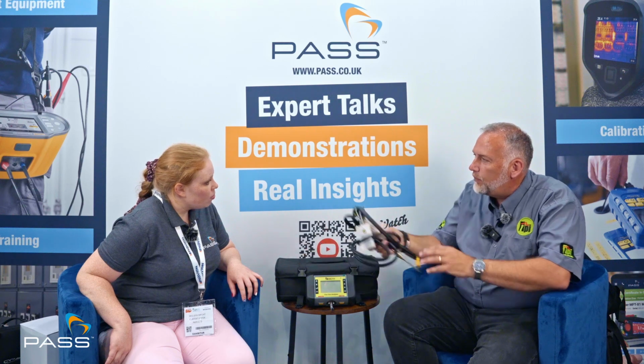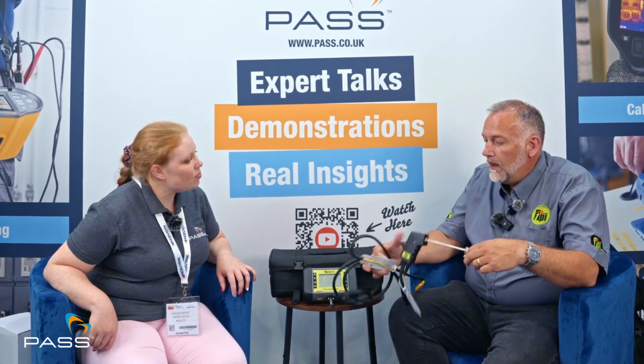Look after the analyzer, and this is the most crucial part, your flue probe. Engineers don't need to put that probe all the way into a boiler anymore. That's designed for when we have to go outside. Boiler manufacturers put flue sampling points, so it only goes in that far, it's not hitting the back. When that's in the bottom of the boiler, that's hitting water, and it'll just pull it in. So whatever brand you've got, that depth stopper is critical.